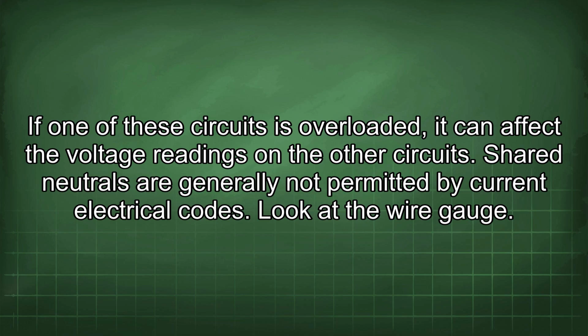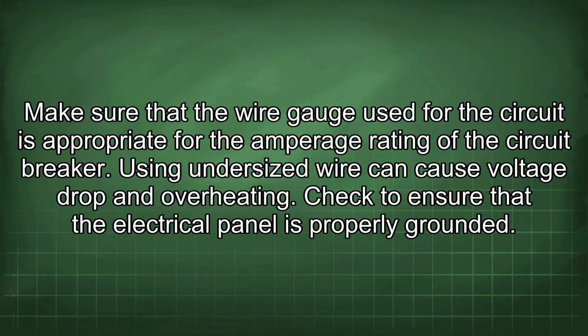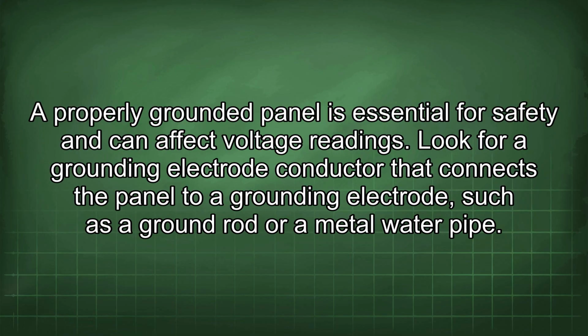Look at the wire gauge. Make sure that the wire gauge used for the circuit is appropriate for the amperage rating of the circuit breaker. Using undersized wire can cause voltage drop and overheating. Check to ensure that the electrical panel is properly grounded. A properly grounded panel is essential for safety and can affect voltage readings. Look for a grounding electrode conductor that connects the panel to a grounding electrode, such as a ground rod or a metal water pipe.